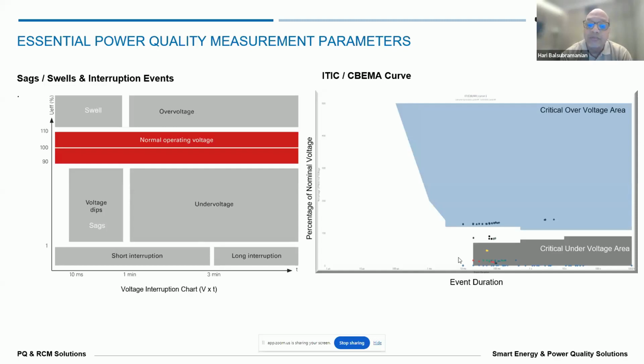And then we could look at possible solutions to reduce these kinds of events so that the equipment we use is safer. Say, for example, if a voltage low occurs constantly for 100 milliseconds, I'm just giving an example, and the voltage goes low around 50% for very few cycles. 100 milliseconds is 5 cycles approximately. So our motors can take higher current during these times. The VFDs will not know why the voltage is going low, and then it can behave erratically.